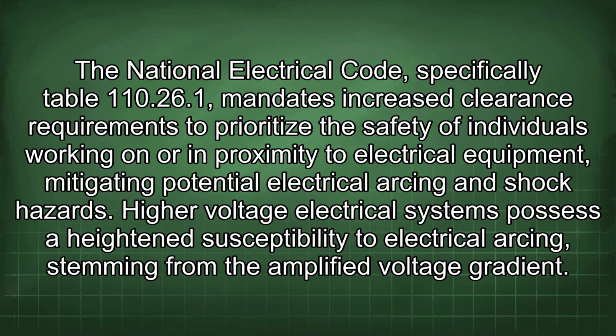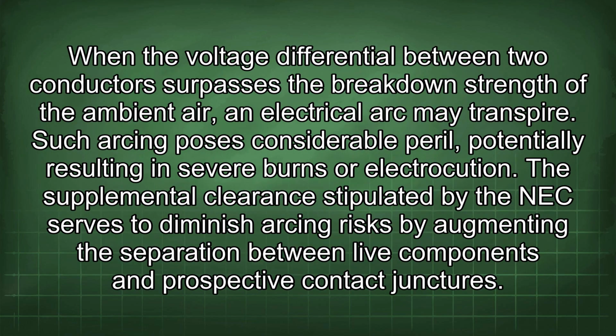The National Electrical Code, specifically Table 110.26.1, mandates increased clearance requirements to prioritize the safety of individuals working on or in proximity to electrical equipment, mitigating potential electrical arcing and shock hazards. High-voltage electrical systems possess a heightened susceptibility to electrical arcing, stemming from the amplified voltage gradient. When the voltage differential between two conductors surpasses the breakdown strength of the ambient air, an electrical arc may transpire. Such arcing poses considerable peril, potentially resulting in severe burns or electrocution.